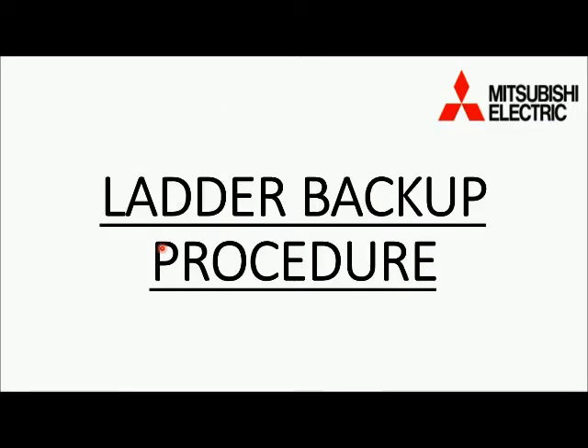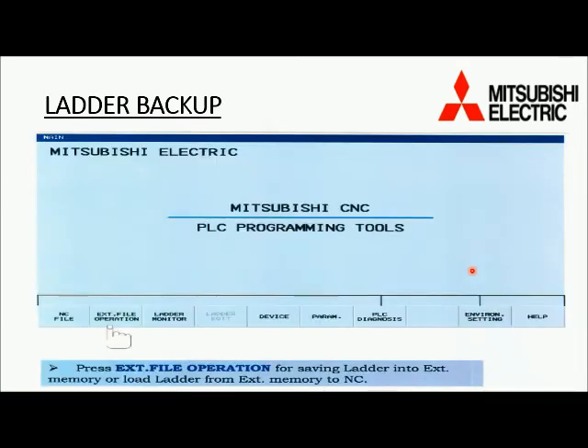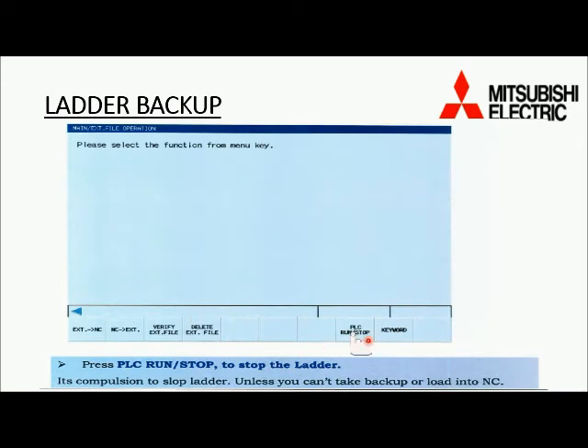Now we come to the last procedure, which is ladder backup. For ladder backup, press F0 from the keyboard. The ladder backup screen will appear. Note: for ladder backup you have to input the password MPA in the password input screen. Then the second option is extension dot file operation — press it. Next, the second option is PLC run/stop — press it to stop the PLC before taking the backup.